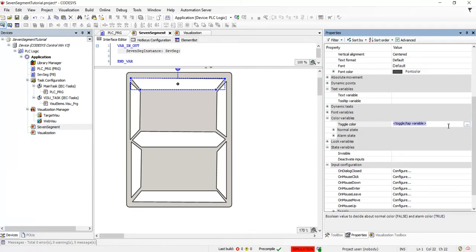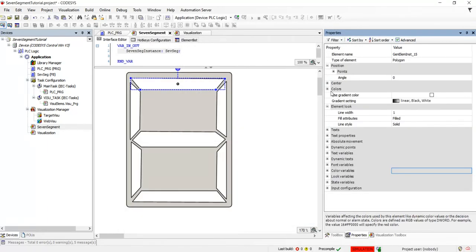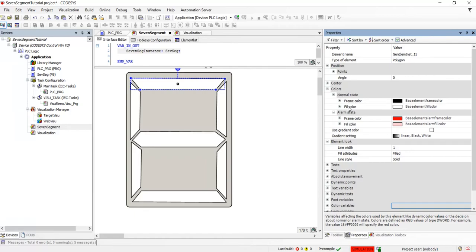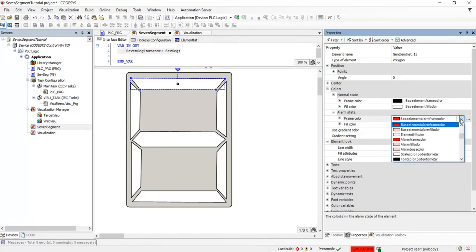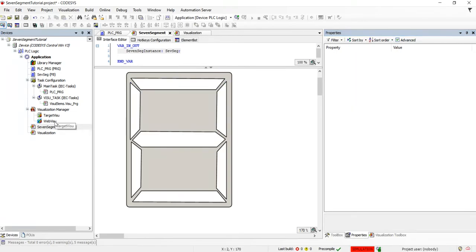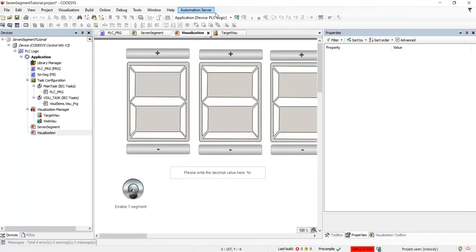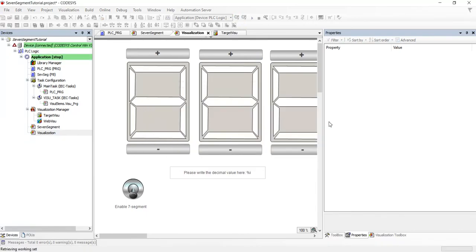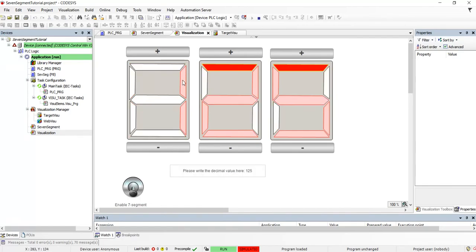For the color variable we associate the toggle color with the variable - the first one will be 'segment A'. We check the colors: for the normal state we keep the default, and for the alarm state we set the fill color. We can change this to red and yellow. We need to do this for all other segments. Important to keep in mind is that in the target visualization you need to have the visualization written there. Now let's see what happens when we log in and download the code - let's change the number to 125 and we see that 125 is displayed.